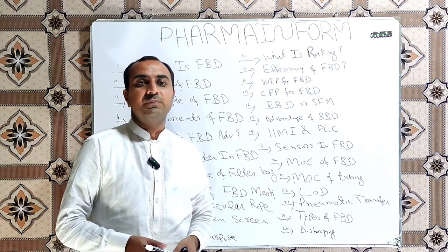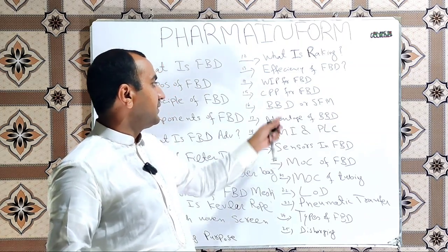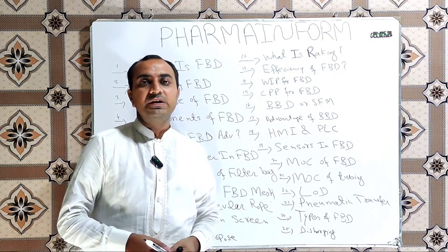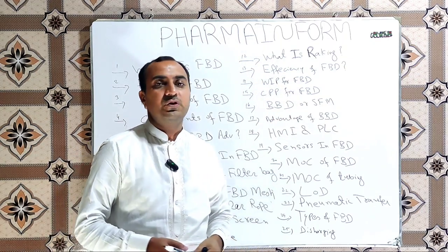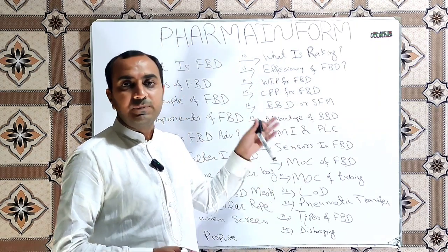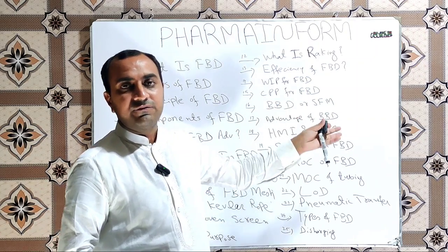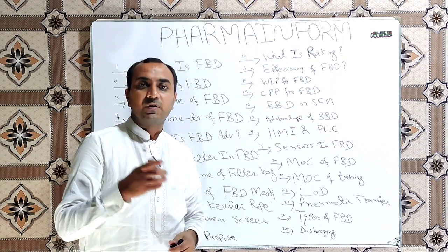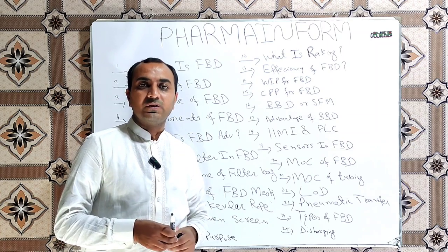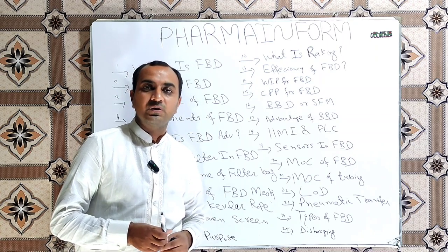Next one is what is BBD or what is SFM. BBD is broken bag detector and SFM is solid flow monitor. BBD basically or SFM is a sensor which works to prevent the product loss and shut down the dryer.